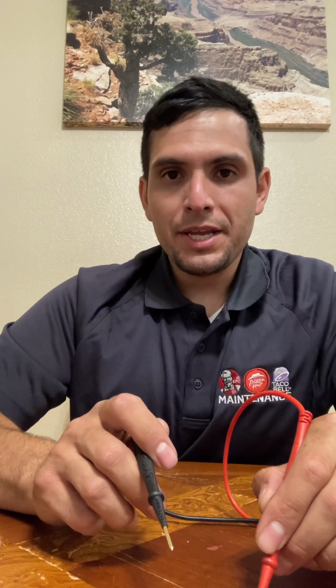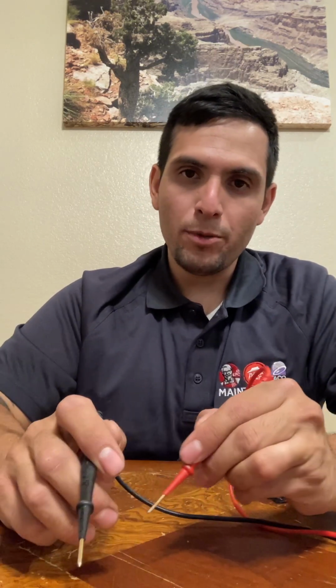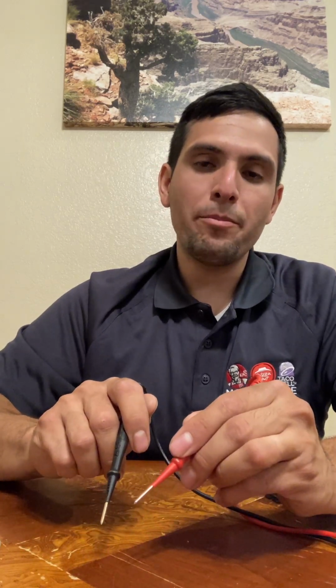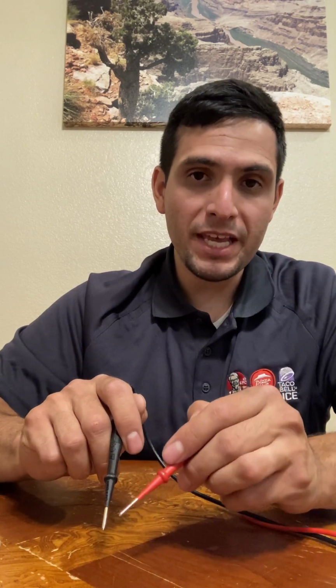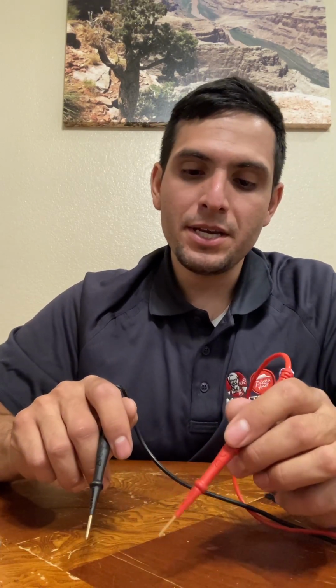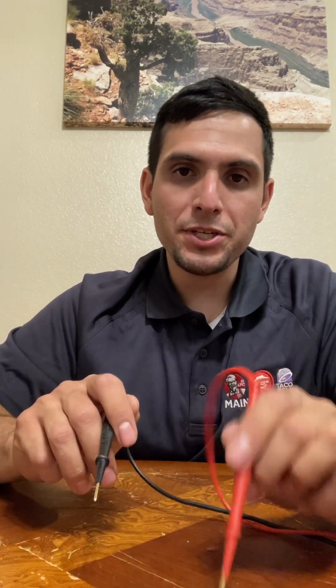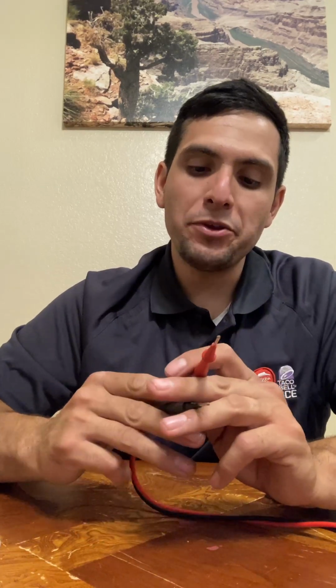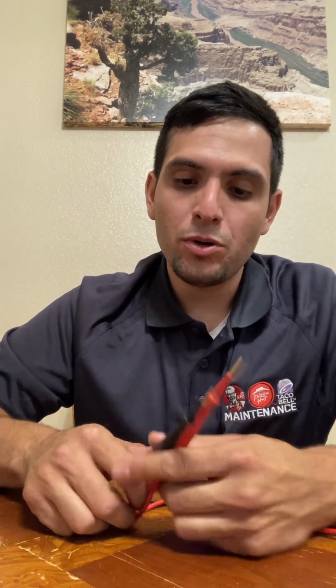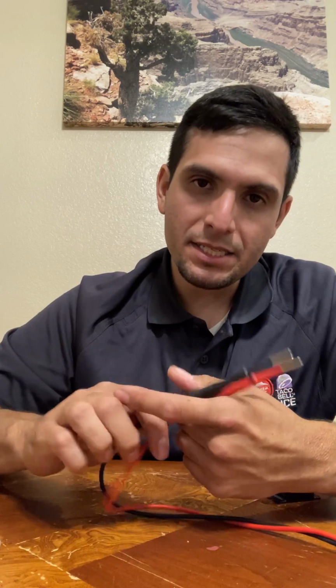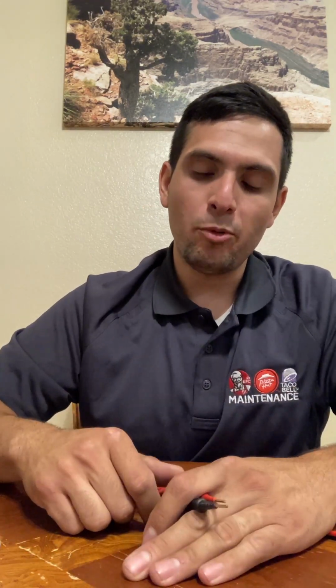But basically, if you're getting over 13 volts coming out of that transformer to your board, your board may not operate right. Sometimes it'll be doing that and the board will still work, but then intermittently you'll have problems. So check that voltage going to your board. You should not have more than 13 volts DC going to your board. If you do, it can cause the board to do wonky things. It can cause your relays to do wonky things. So check that. And then finally, if you checked your transformer, your relays, your probes, and there's nothing else, then the manufacturer says it might be the board. And they don't have a specific troubleshooting for the board. It's basically eliminate everything else and then the board last.